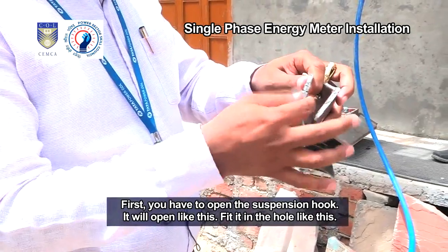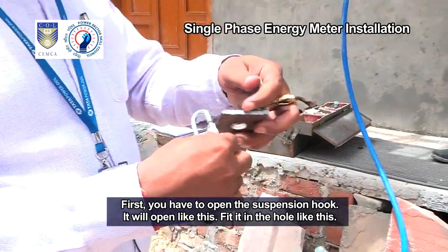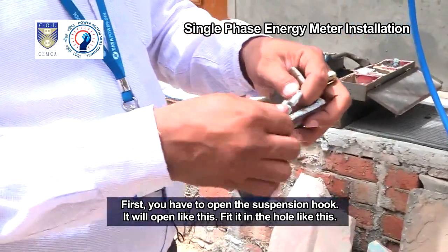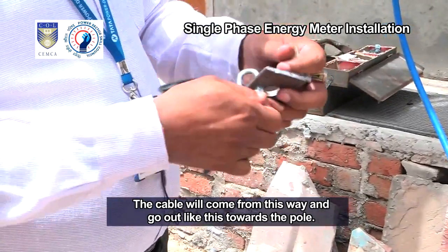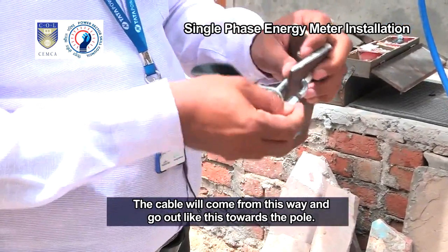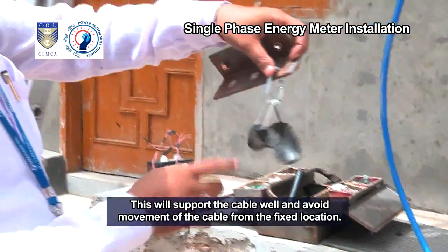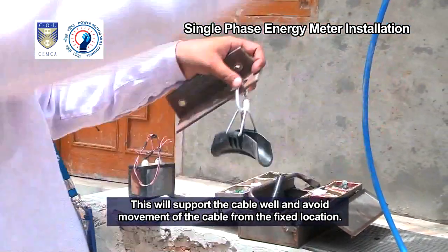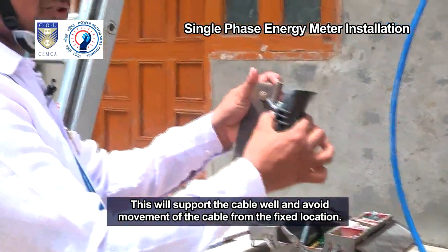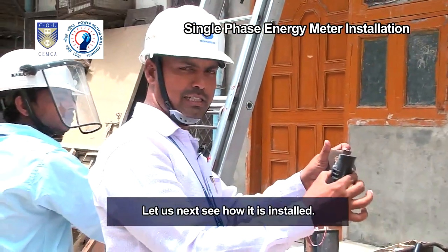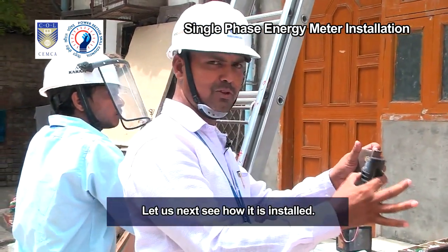First, you have to open the suspension hook. It will open like this, fit in the hole like this. The cable will come from this way and go out like this towards the pole. This will support the cable well and avoid movement of the cable from the fixed location. Let us next see how it is installed.